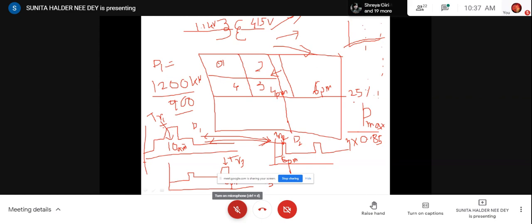Along with that, this load will be available at the load end, and the transformer is far away from there because there are some distributors in between. So there is some line loss, and I am assuming 25% for that. Why 25%, not 5%? Because in a distribution system, loss is far higher than in a transmission system. So the total expansion I have taken is 50%. So we shall multiply by 1.5 to get the actual data. Understood?